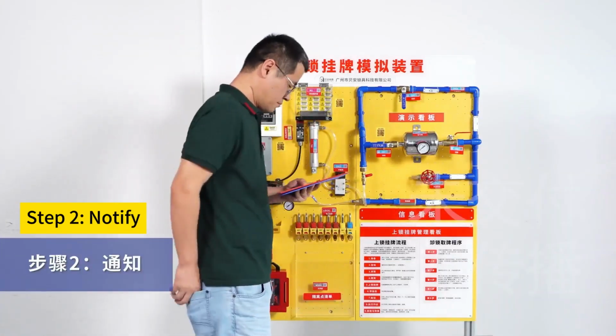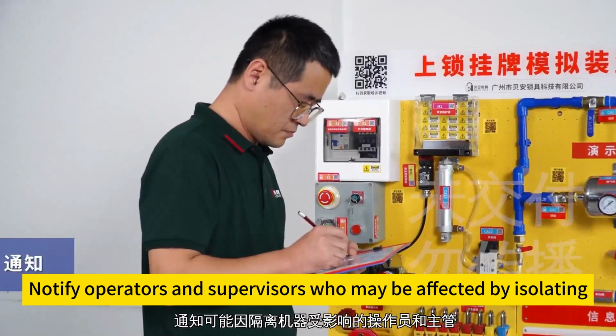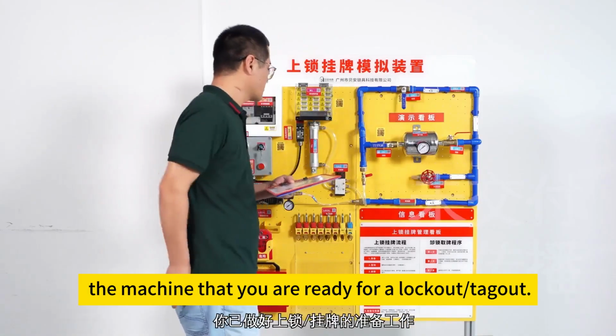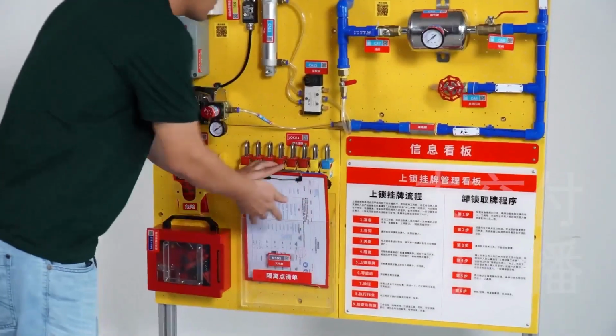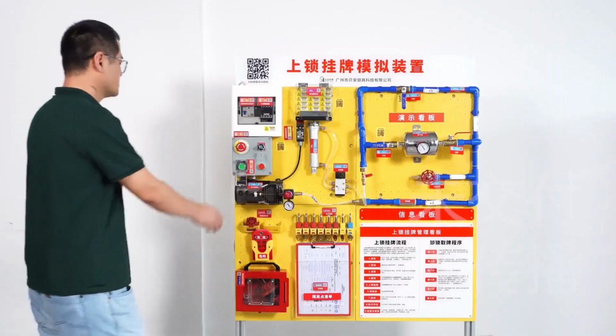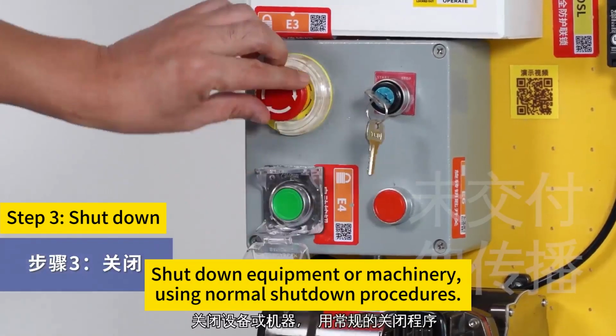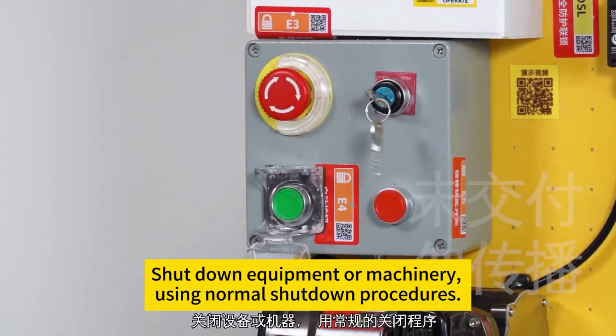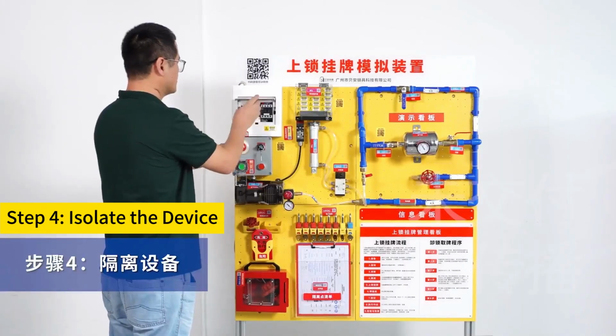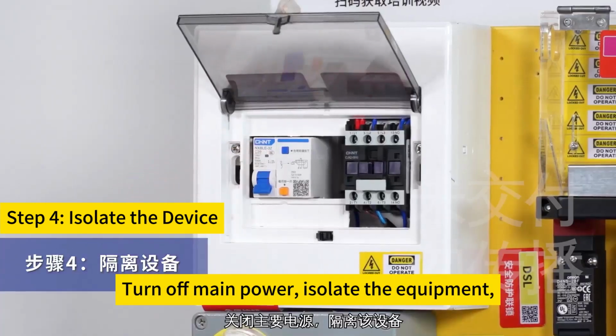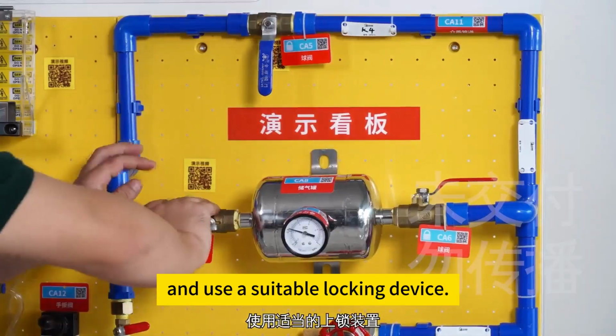Step 2. Notify. Notify operators and supervisors who may be affected by isolating the machine that you are ready for a lockout / tagout. Step 3. Shut down. Shut down equipment or machinery using normal shutdown procedures. Step 4. Isolate the device. Turn off main power, isolate the equipment, and use a suitable locking device.